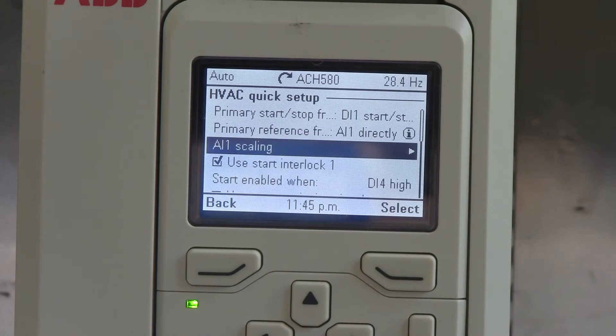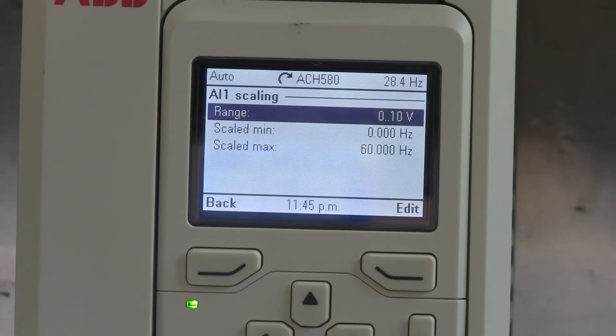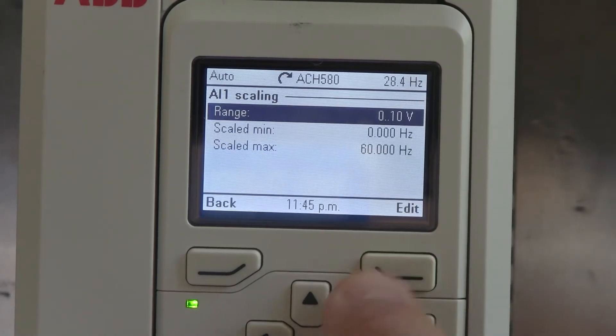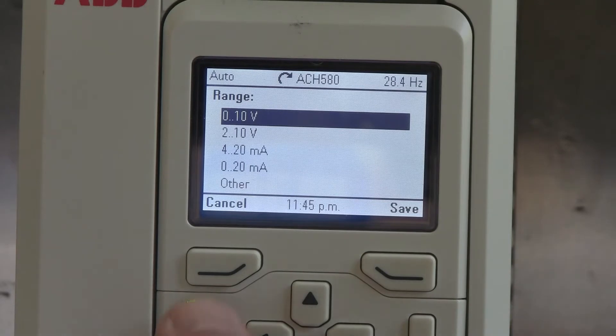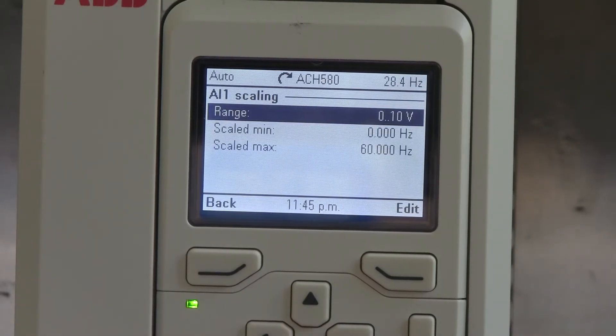If you had to scale it, change it from a 4 to 20 to a 0 to 10 or something like that, hit the right arrow one time and then you can change the range. So if we edit that, we can change from a 0 to 10, 2 to 10, 4 to 20, and so on. It's got a lot of choices there, so we'll cancel out of that. We'll leave it for 0 to 10, and the range is 0 to 60 Hz.